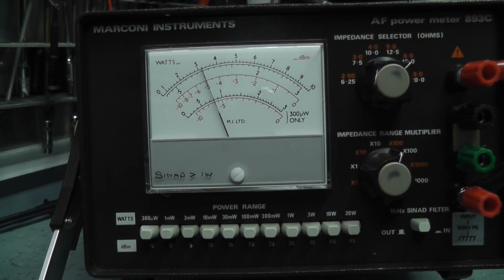So it's working well. The other thing to mention about this is the Sinad function - signal to noise and distortion - a test used for checking sensitivity of receivers, particularly after the 80s. Sinad, however you want to say it, was a method of feeding in a 1 kilohertz tone and looking for the tone being resolved over the noise floor of the receiver. What it does is introduce a notch filter. On normal meters, it introduces a notch filter, and it can differentiate between the 1 kilohertz tone getting through and the background noise, and that gives you the Sinad reading.